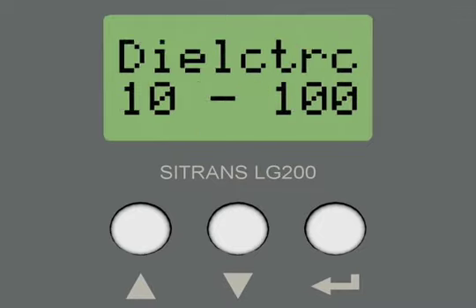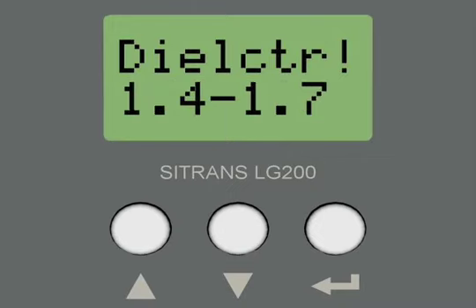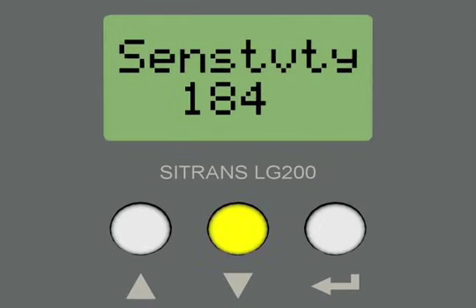The dielectric constant parameter needs to be adjusted to optimize the sensitivity of the unit for our application. For the twin rod probe, there are 4 dielectric range choices available. Push the down arrow to scroll through the choices. The dielectric range selection of 1.7 to 3 is suitable for our application. Push the up arrow to go back to this selection and then press the Enter key to set this parameter. We will leave the next 2 parameters set to their factory defaults. Push the down arrow key 3 times to skip these parameters.